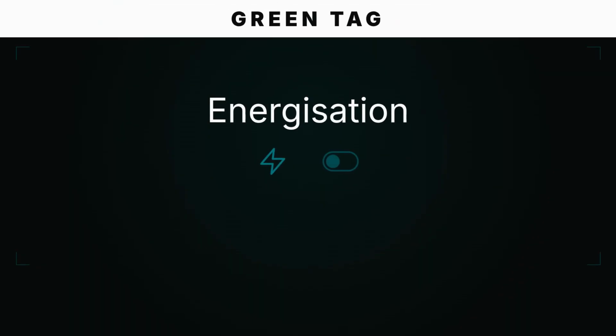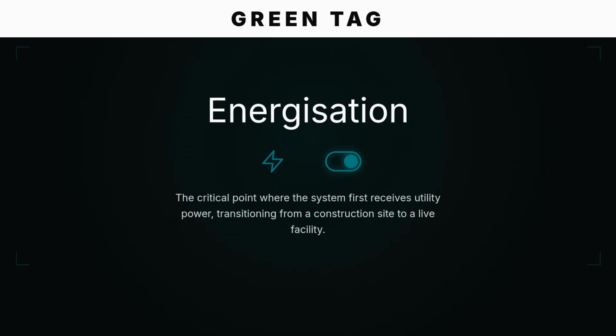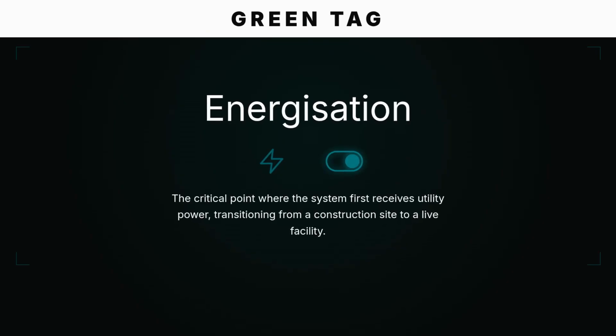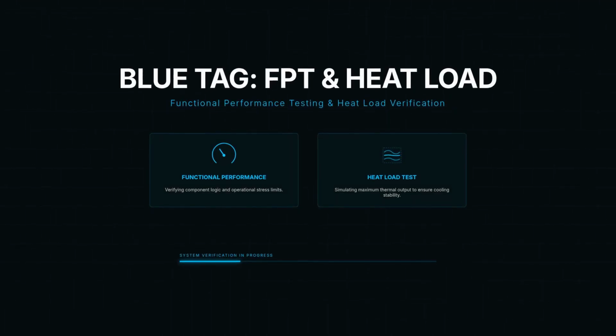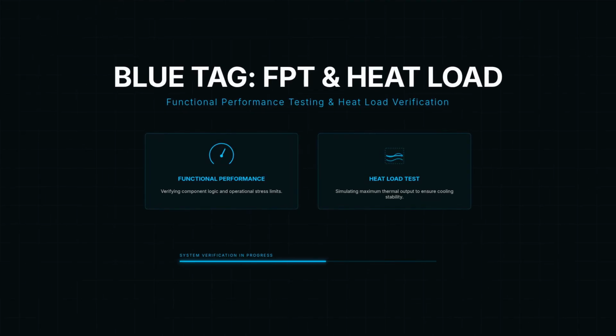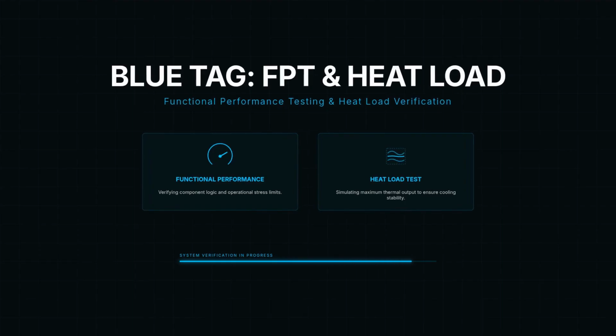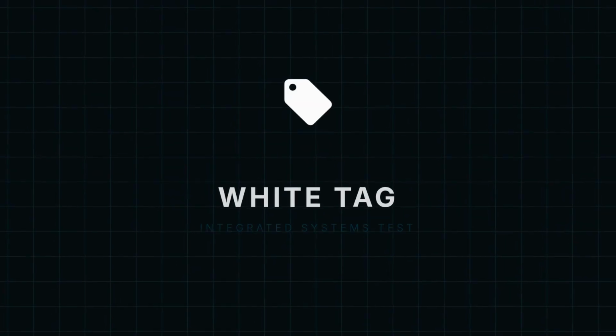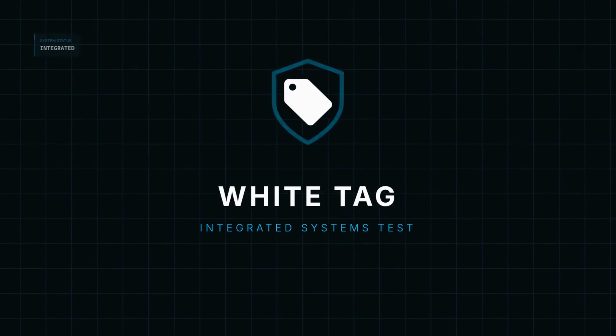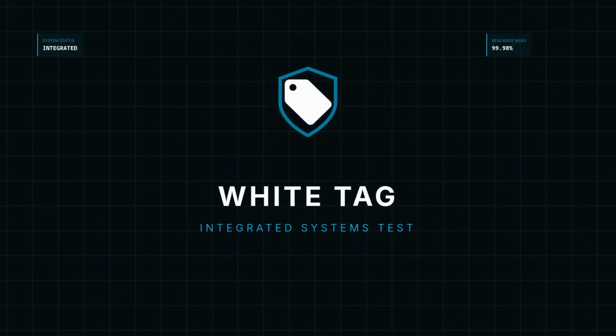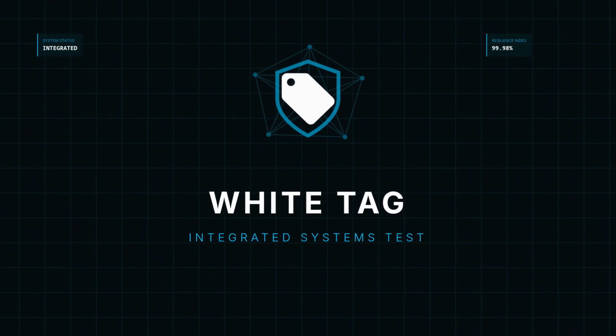Green tag, energization, the critical point where the system first receives utility power, transitioning from a construction site to a live facility. Blue tag, functional performance testing and the heat load test. We verify that every component functions exactly as intended under stress. White tag, the final integrated systems test. This is where we prove the resilience of the entire campus as a single unified machine.